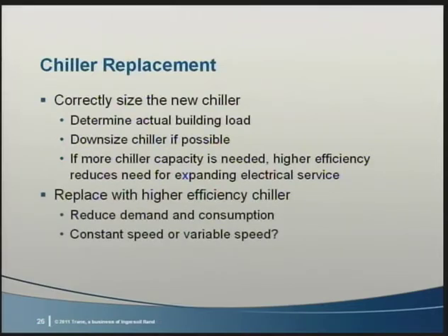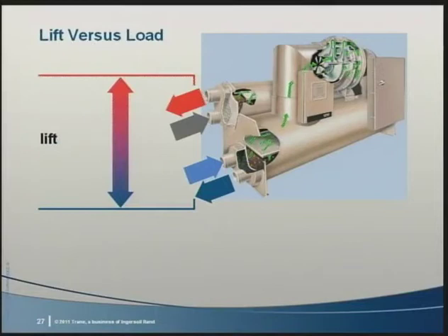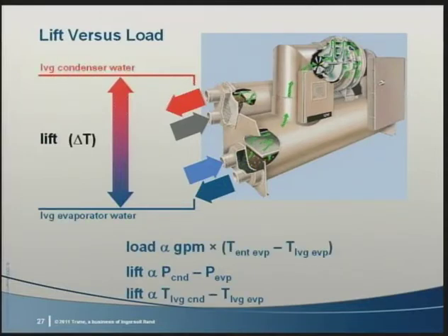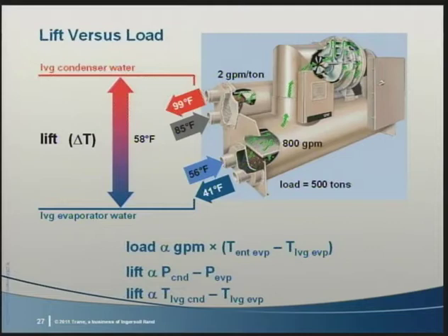And when considering which chiller technology is the right fit, the discussion turns to the circumstances that benefit constant or variable speed technology. Here's a quick refresher from a past ENL program on VFDs. The load a chiller satisfies is a function of the flow rate and the difference in evaporator entering and leaving temperatures. The lift a compressor must develop is proportional to the refrigerant differential pressure between the evaporator and condenser. In turn, that pressure difference is proportional to the condenser water delta T. In this case, at design conditions, the load is 500 tons and the lift is 58 degrees. Load and lift are related to total compressor work, ultimately corresponding to the amount of potential energy savings.